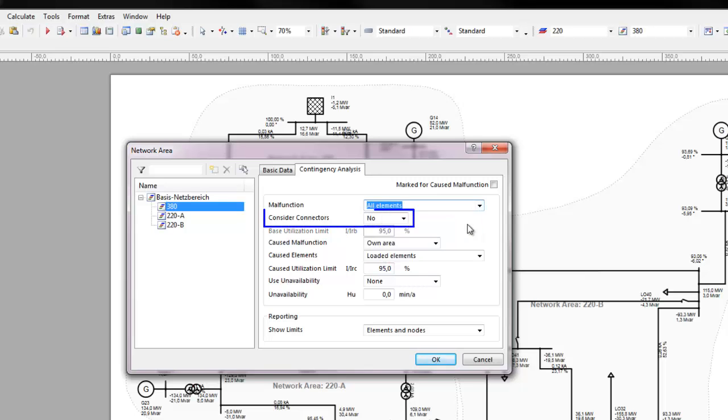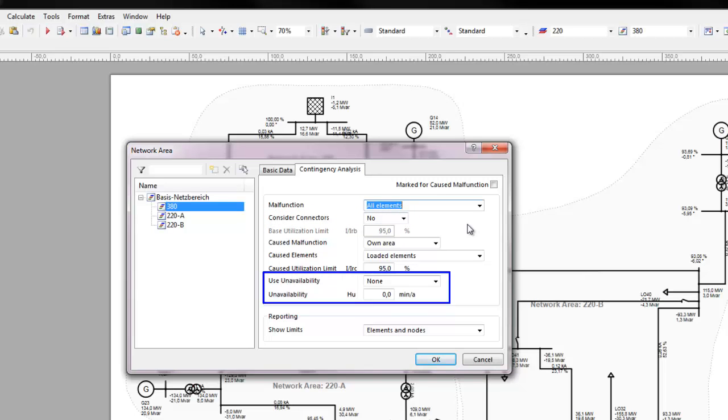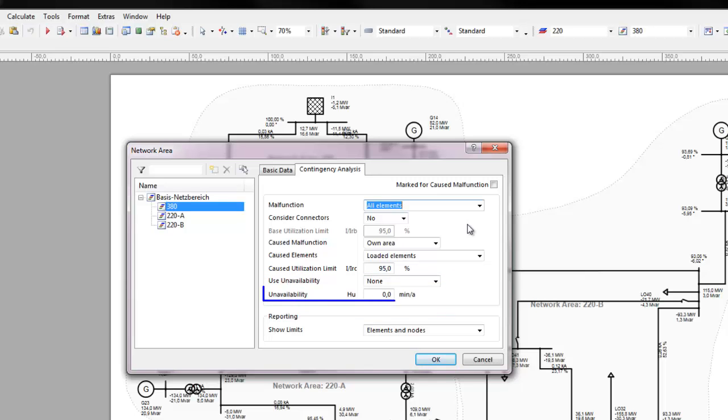It is possible to specify whether connectors are considered to malfunction or not. The availability of elements, as defined in the settings for reliability calculations, can also be incorporated into the Contingency Analysis. This availability condition provides a probabilistic approach to limiting malfunctions. A limit value can be set in unavailability to limit the number of simulations.